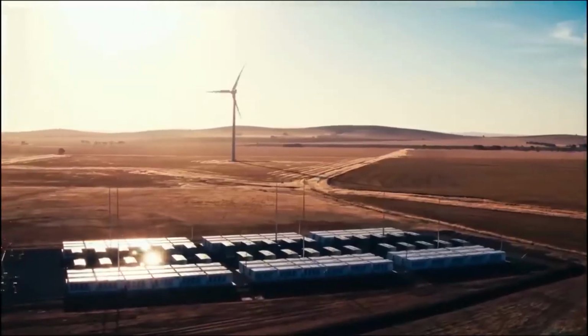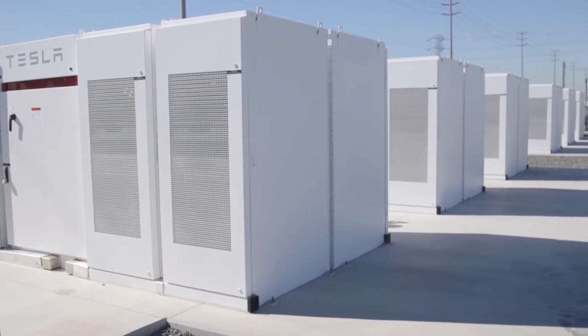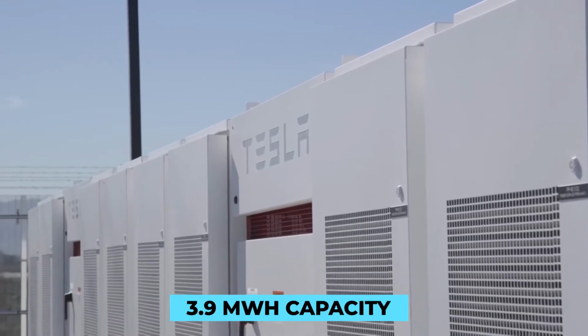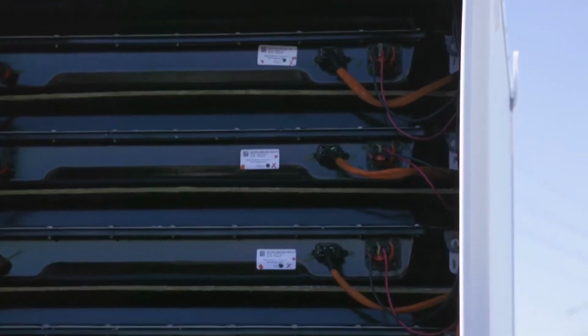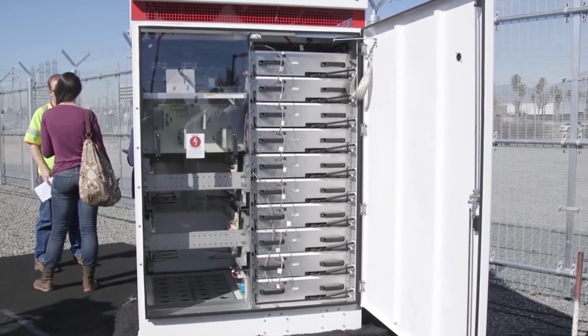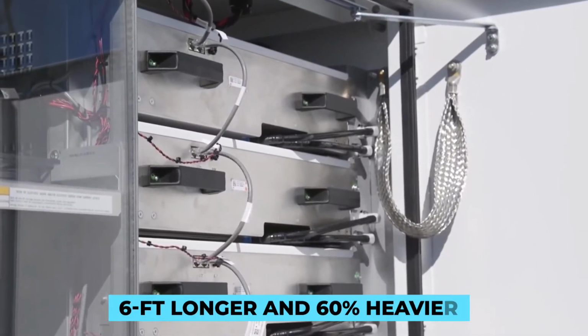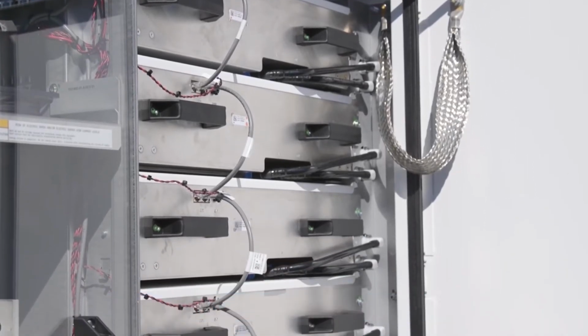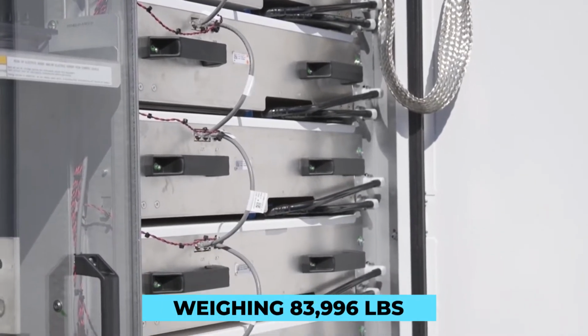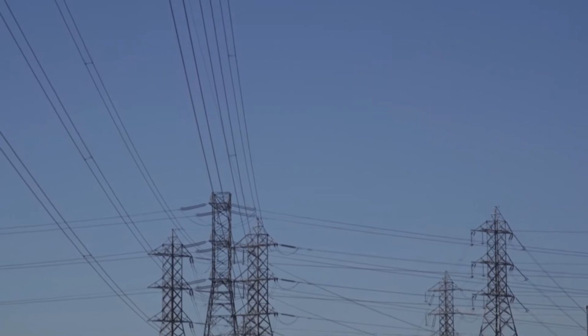Tesla recently updated its Megapack configuration to list a 3.9 megawatt-hour capacity. This results in a single Megapack having around 50% greater energy capacity. But the battery system is now 6 feet longer and 60% heavier, weighing 83,996 pounds. This would suggest that while the Megapack's energy capacity has grown, its energy density has decreased.